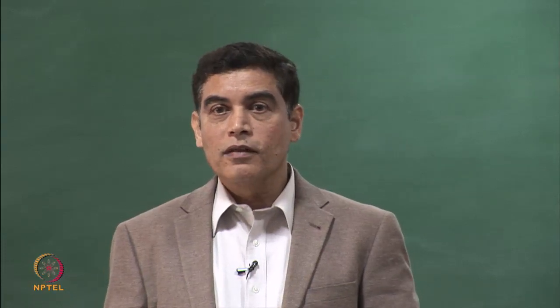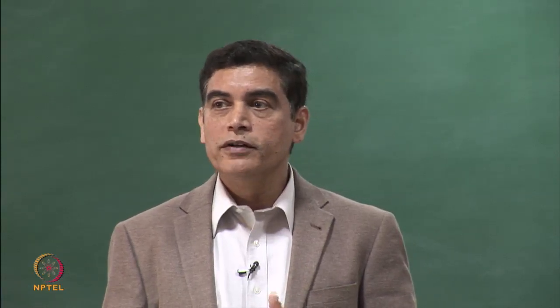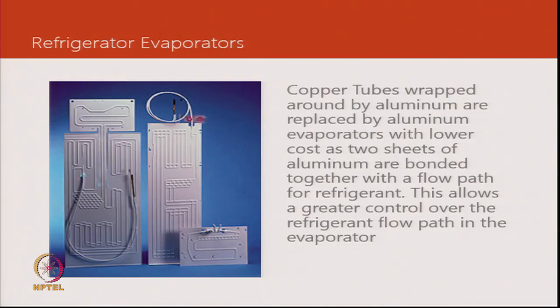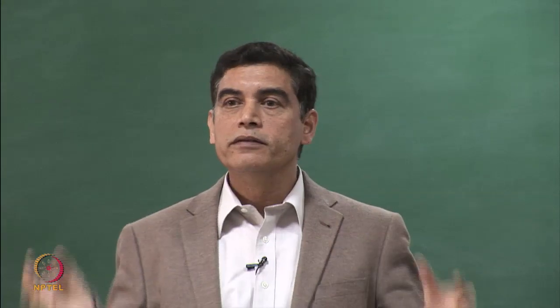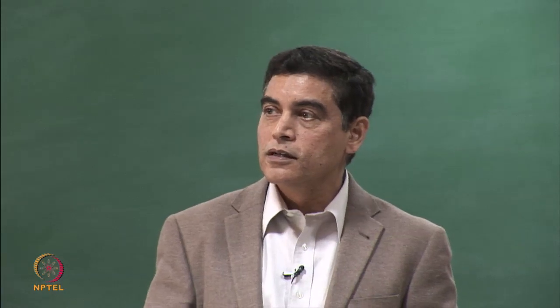Before the suction line reaches the compressor, there may be an accumulator to handle any surge or refrigerant droplets of R134A or R12. When designing a refrigerator evaporator, the refrigerant flow path is defined — the lines visible on the roll-bond evaporator represent the refrigerant path. The component is shipped flat and then formed by bending into a C-section or rectangular section to create the freezer, forming the basic heat transfer component inside the refrigerator.